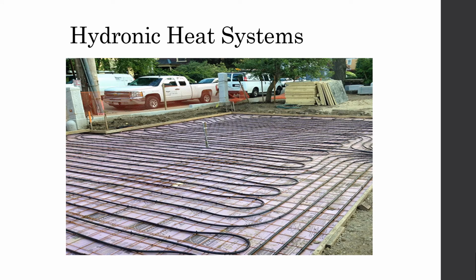After considering multiple design possibilities, it became clear that a hydronic heat system would be a suitable alternative to prevent the accumulation of winter precipitation on Winegard Ramp. A hydronic heat system facilitates the heat transfer between a working fluid and an area that is to be heated. Simply put, warm liquid flows through piping buried within the ramp, as seen in the figure on the screen.